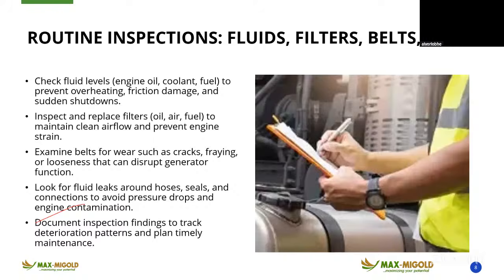All right. Routine inspection: fluid, filters, belts, leaks. These are the things you check on routine inspection. They are very small things, very minute, but you have to make sure attention is given to them. Check fluid levels, that's engine oil level, coolant level, fuel level, to prevent overheating, friction damage, and sudden shutdown. If the levels are short beyond the sensor gauge, it will shut down. If there is a shortage of water in your radiator, the engine will overheat. It will shut down and you start spending money that you are not meant to spend.